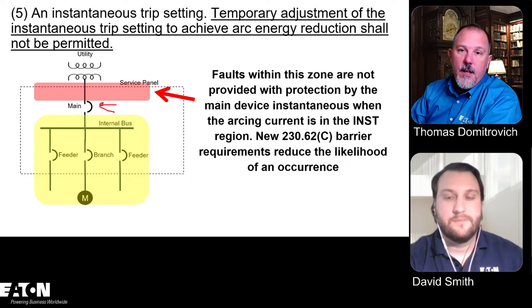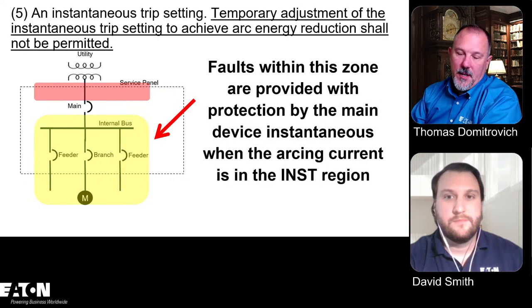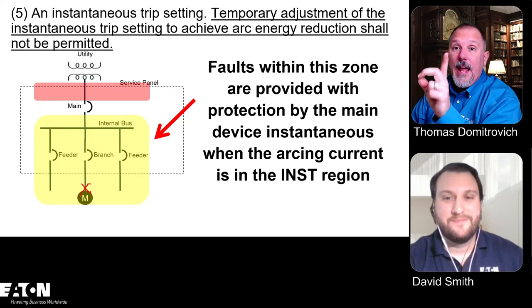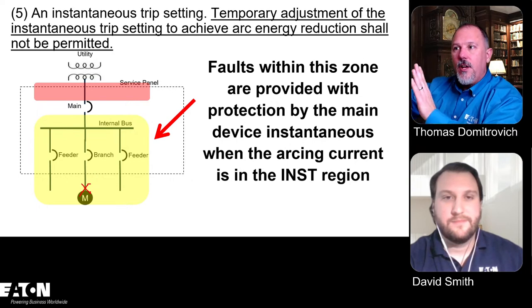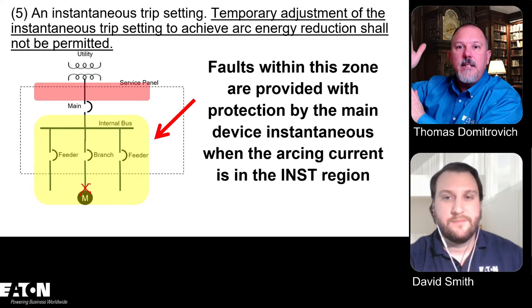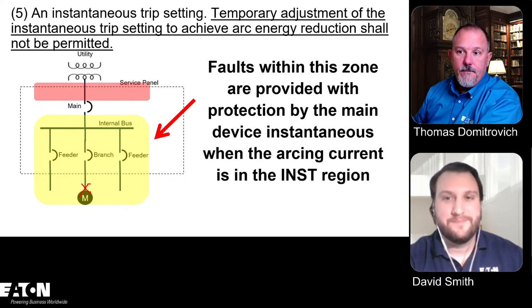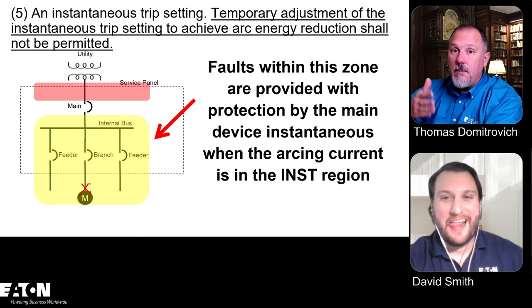This breaker here, if I'm working in the instantaneous range, will protect downstream. How far downstream will depend on, say, if I have a fault at this motor, that length of conductor. If my arcing current at that motor is still in the instantaneous region of that breaker, I'm still providing arc reduction for that motor. Right? Now, if I have a very long run, I'm not going to provide any protection. So that's important. Instantaneous on a molded case circuit breaker is at least 10 times the handle rating. So a 1200 amp breaker would be 10 times, right? Is that right, 1200 or 12,000 amps? There you go, 12,000 amps would be your minimum instantaneous region.